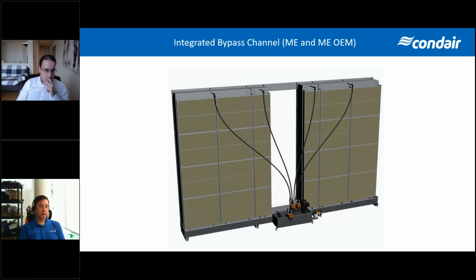Next slide, Nuno. Again, very similar. This is also an OEM unit, but one of the requirements here was to actually integrate a bypass damper for control of the leaving air conditions. So one of the ways that we typically control our ME system is just by turning on individual stages of pumps. On a large unit, we can have up to 7 stages of individual control. If a client is looking to use bypass control and just operate the unit as on-off, and using bypass air and mixed air downstream to control the leaving air conditions, we can do that as well. This client in particular had a requirement to integrate a bypass damper in between 2 banks of evaporative media.